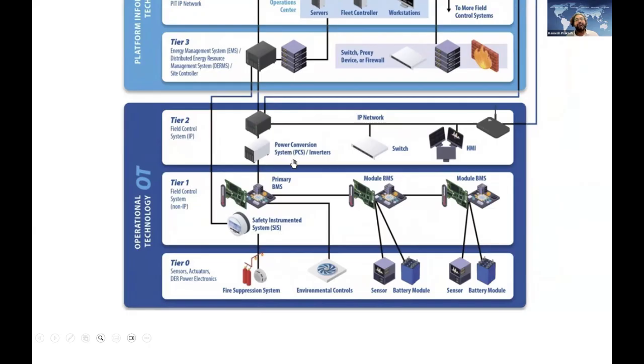Then again, field control system which is IP control - that's tier 2, where our PCS comes into picture because the PCS needs to communicate. For example, the battery may be from CATL or Samsung, but your inverter is from ABB. They both need to communicate with each other to have perfect harmony, either using Goose, or power over Ethernet PoE, or even PLC communication channels. So all systems need to function properly to create a handshake and function in harmony. This is IP-based communication in tier 2.